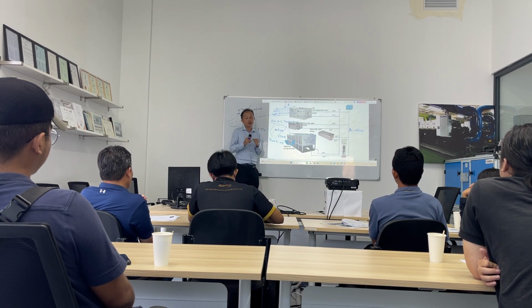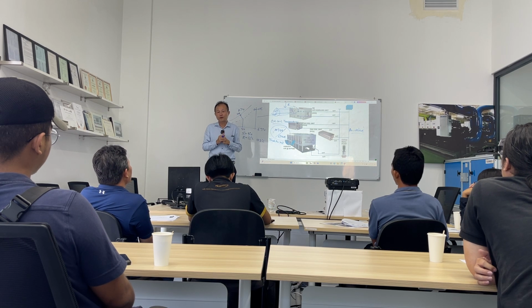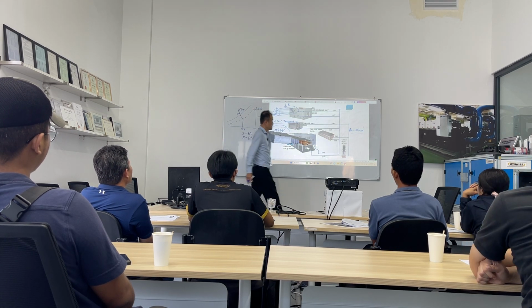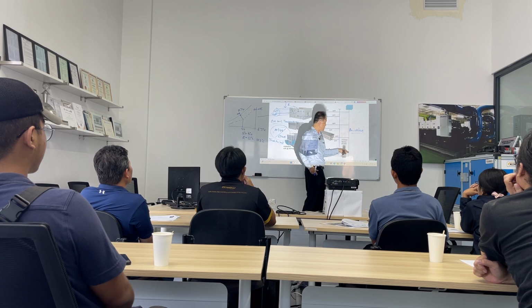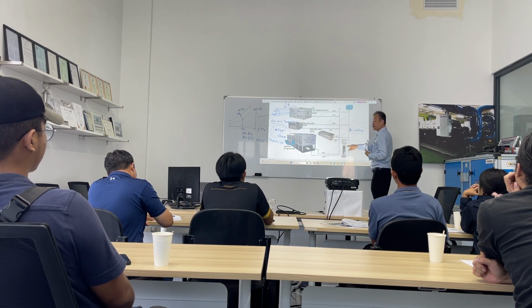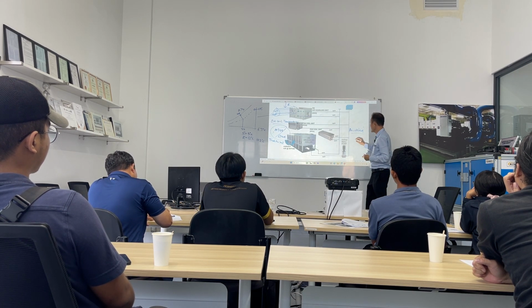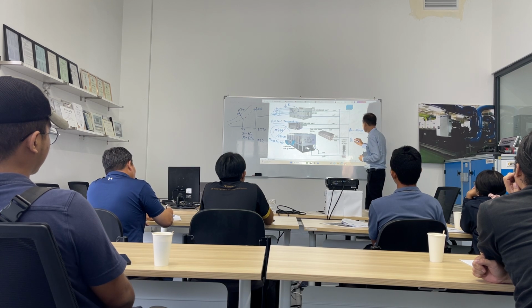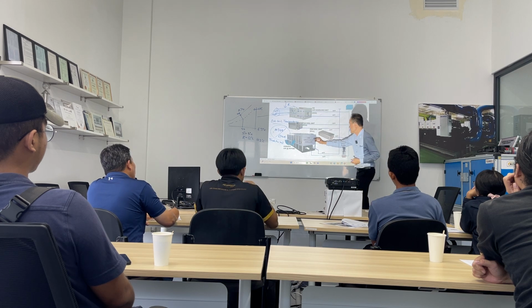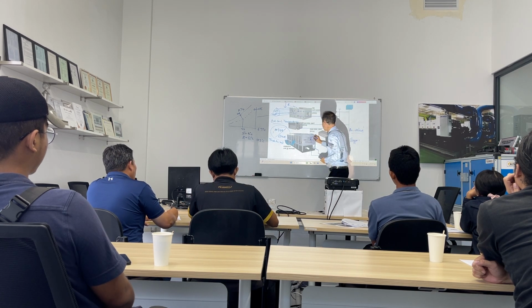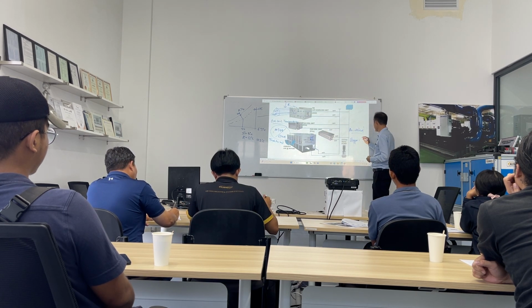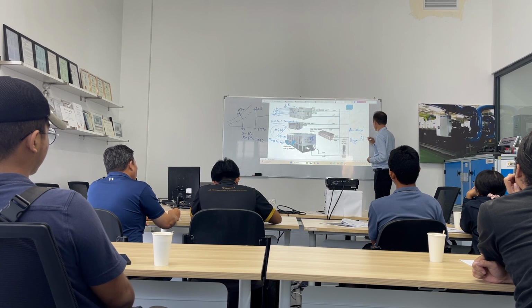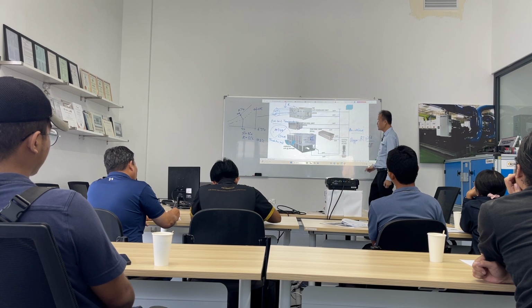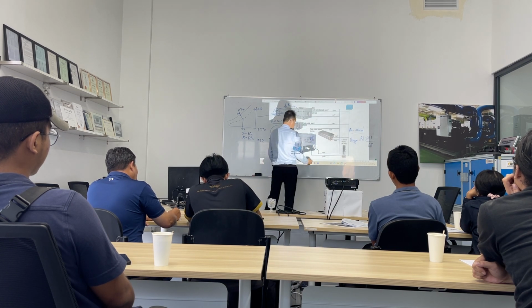Okay, based on this, I would like to share with you some standard formulas to calculate the chill water pump. The chill water pump flow rate, the US GPM, equals the capacity in terms of RT times 24 divided by the delta T.